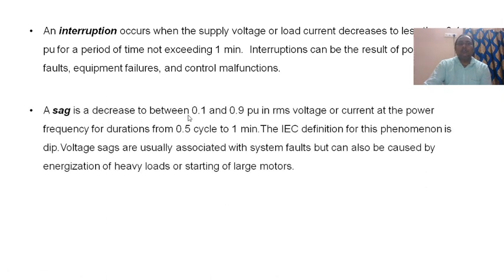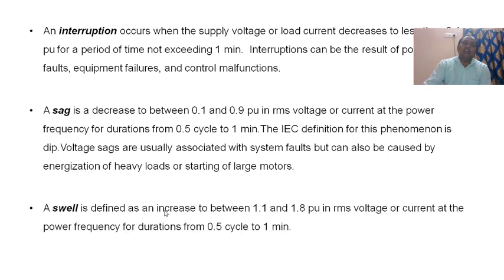A sag is a decrease to between 0.1 and 0.9 per unit in RMS voltage or current at the power frequency for duration from 0.5 cycles to 1 minute. The IEC definition for this phenomenon is dip. Voltage sags are usually associated with system faults but can also be caused by energization of heavy loads or starting of large motors. A swell is defined as an increase to between 1.1 per unit to 1.8 per unit in RMS voltage or current at the power frequency for durations from 0.5 cycles to 1 minute.